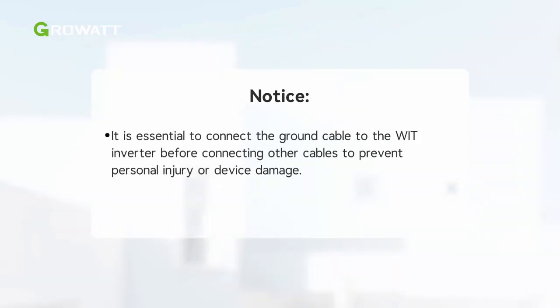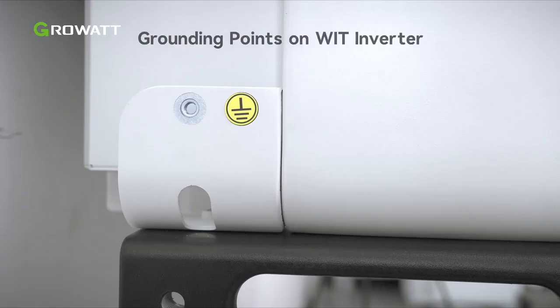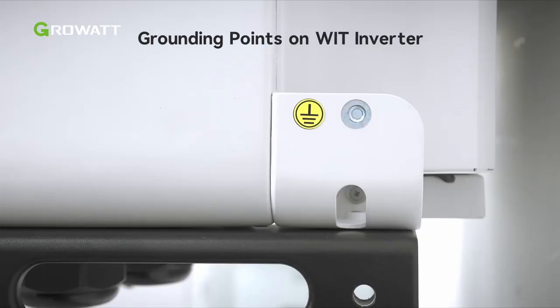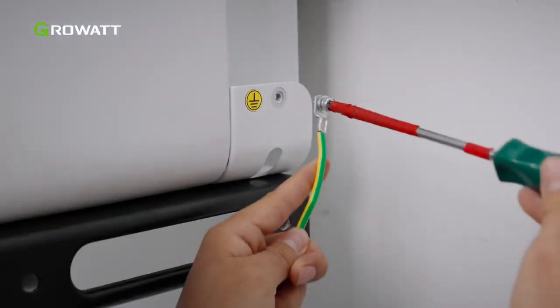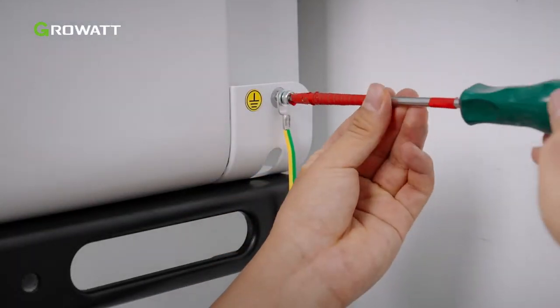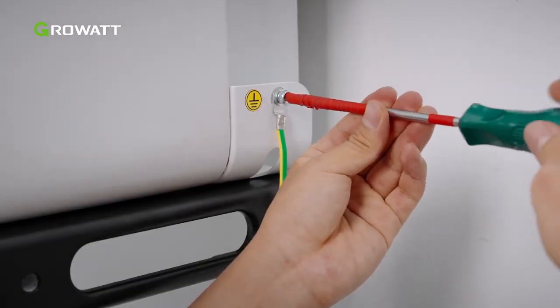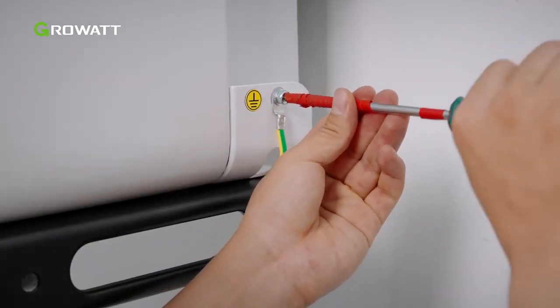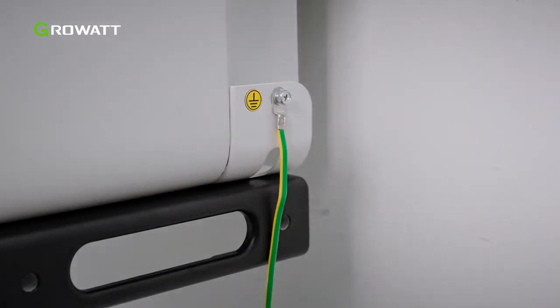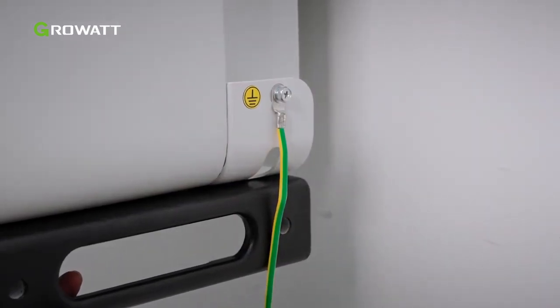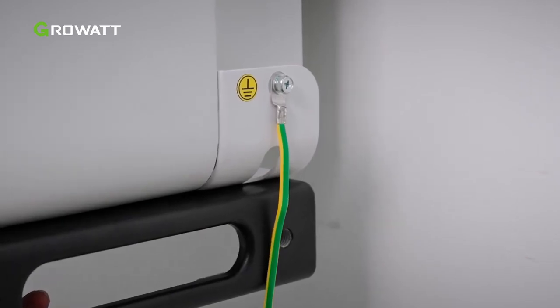It is essential to connect the ground cable to the WIT inverter before connecting other cables to prevent personal injury or device damage. Before starting wiring the inverter, make sure it is safely and firmly grounded. The grounding point is on the 2 sides of the inverter, as the figure shows. Connect the ground cable to the ground point on the chassis shell. For a system with multiple WIT inverters connected in parallel, ensure that the grounding points of the enclosures of the WIT-XHU inverters, the metal racks of the PV modules, and the batteries are connected to the same area to achieve equipotential bonding.